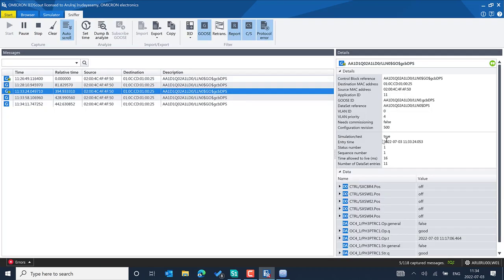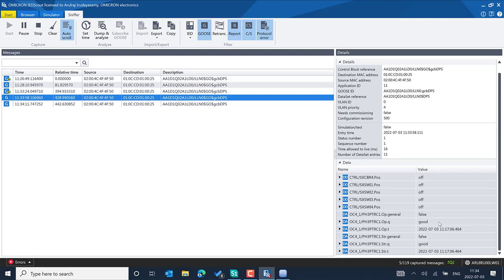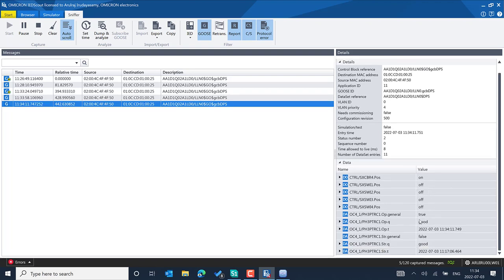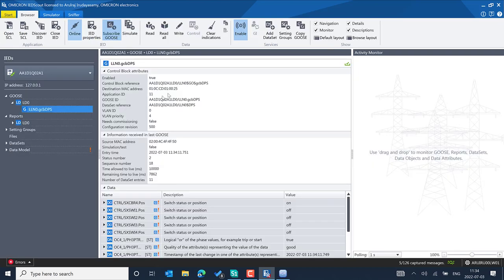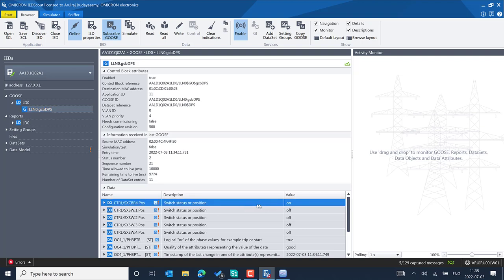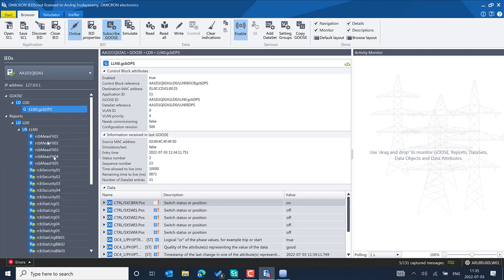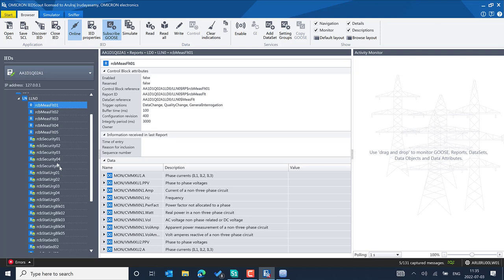The updated value is reflected in the sniffer. The simulation flag is set to false and the value has changed to an intermediate state. The double point status and the protection trip operator PTOC can be simulated from the GOOSE control block. You can see different icons for simulated versus normal GOOSE messages, apply filters, and switch back to the Browser section to enable reports. The subscribed GOOSE messages are received automatically and values are updated — including the switch gear position and circuit breaker trip indication.